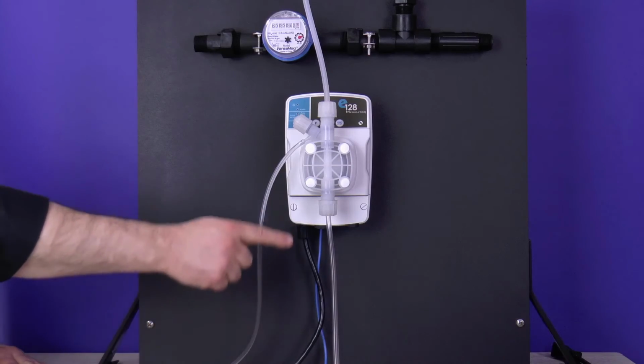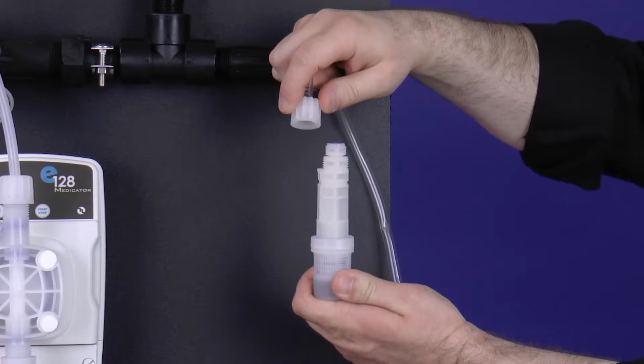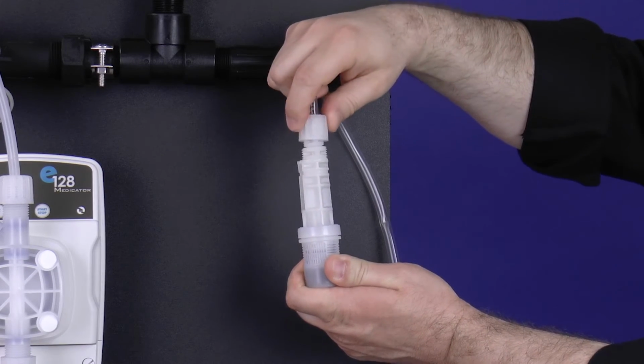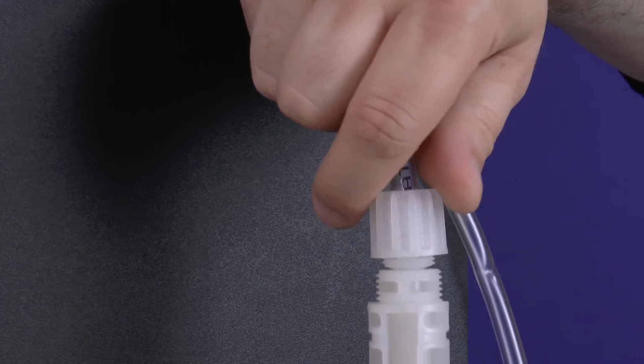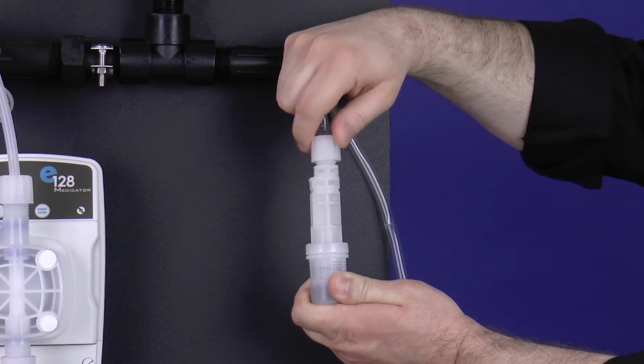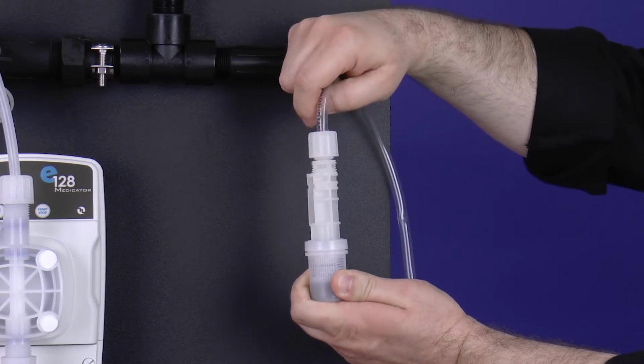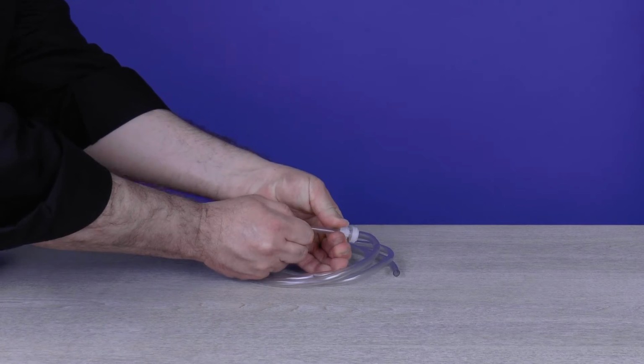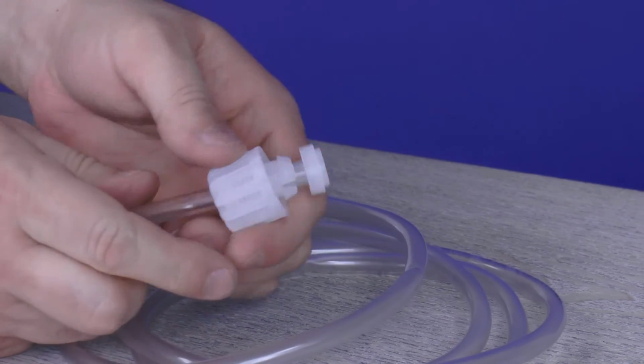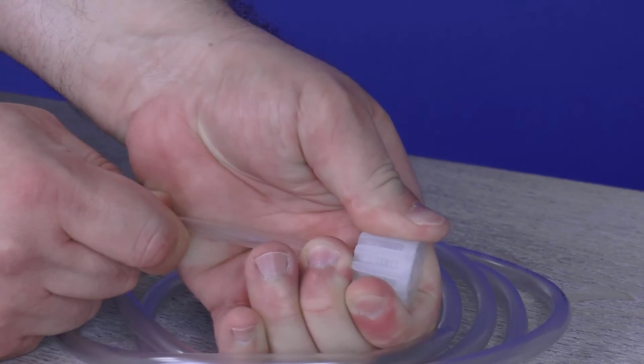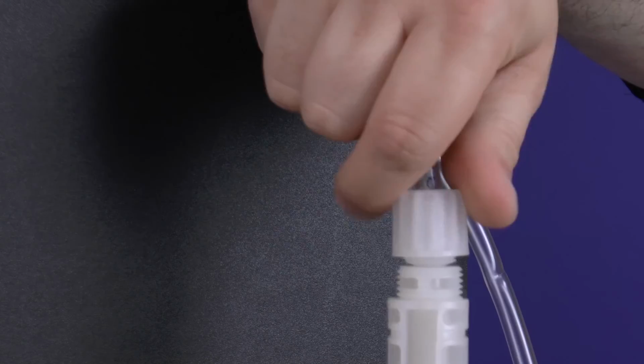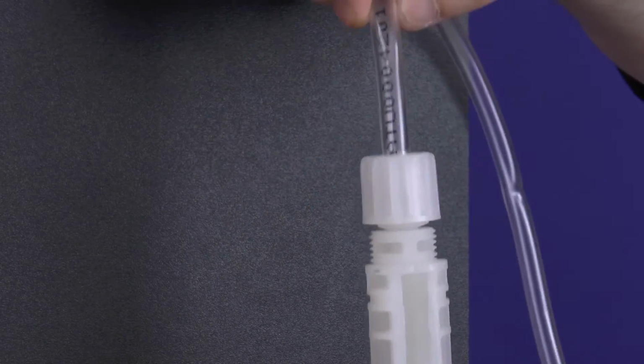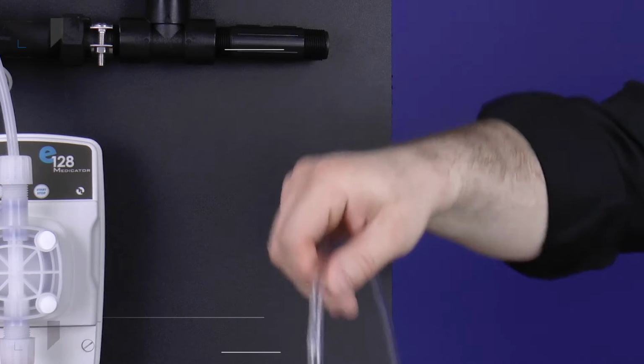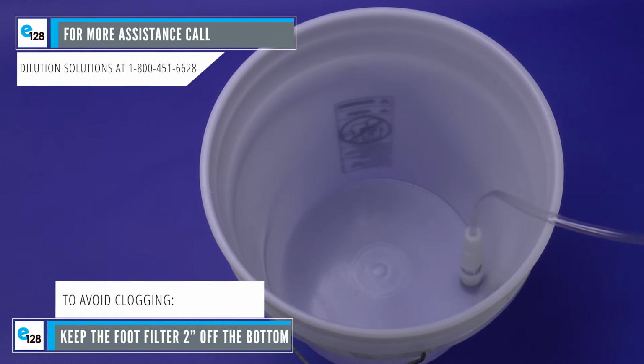Grab the PVC suction tubing hanging down from the suction valve and attach the tube, foot filter tube nut, collar, and nozzle onto the foot filter by hand tightening the tube nut. Do not cross-thread nor over-tighten. If the tube nut is not securing, recheck the ferrule connection. Pull the tube nut toward the nozzle once more to compress the collar and nozzle together. Retighten the tube nut until secure. Place the foot filter into the bucket or stock tank. This ensures the foot filter draws chemistry once you begin operation.